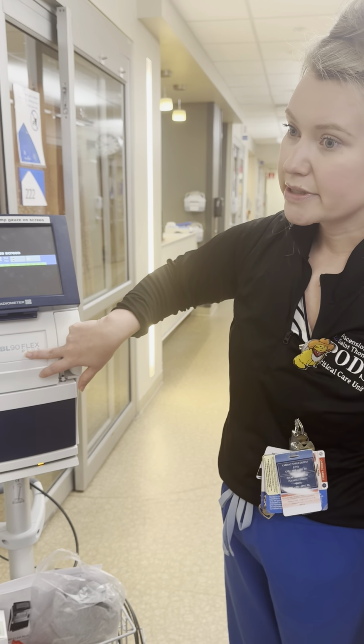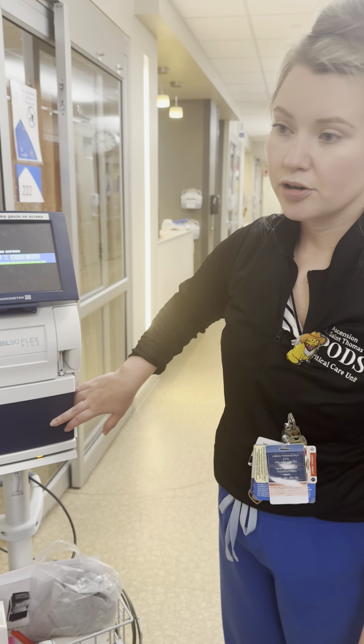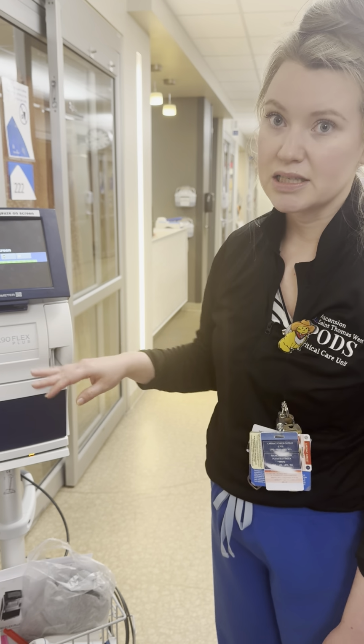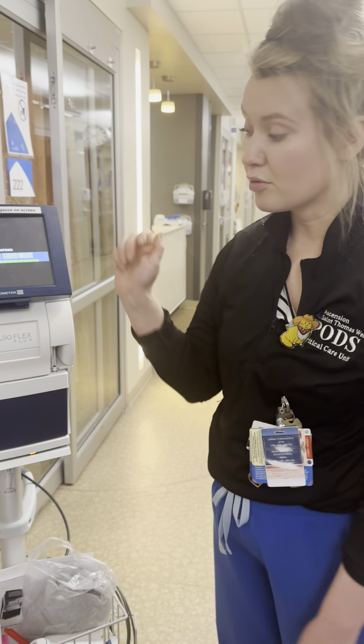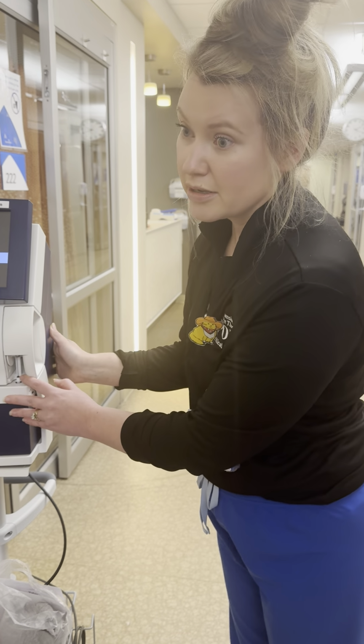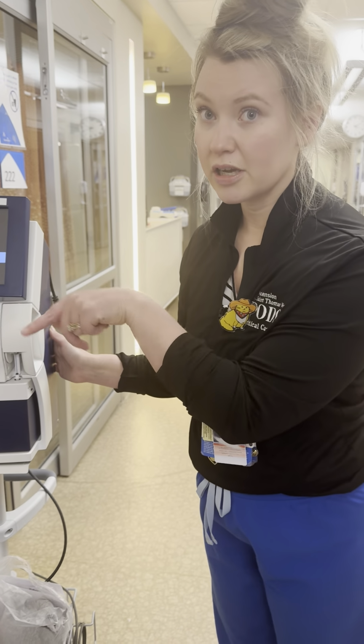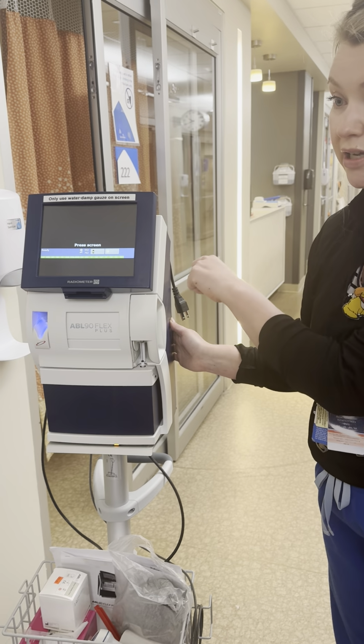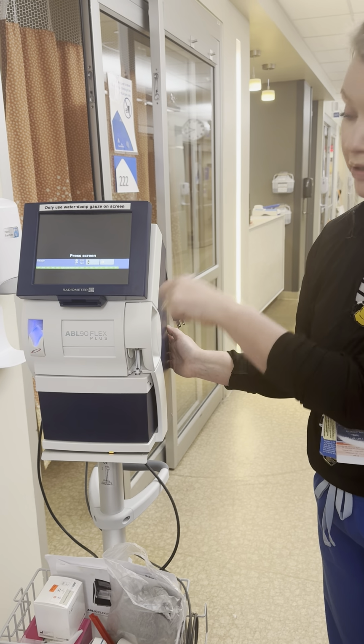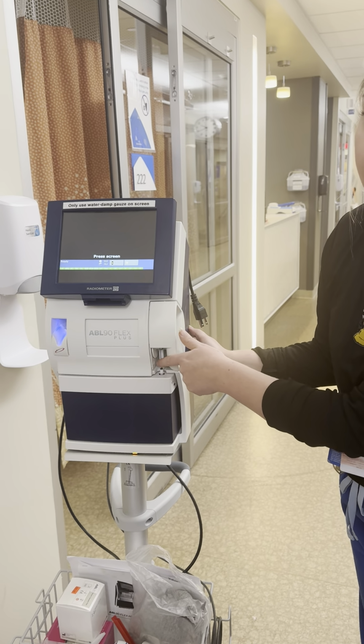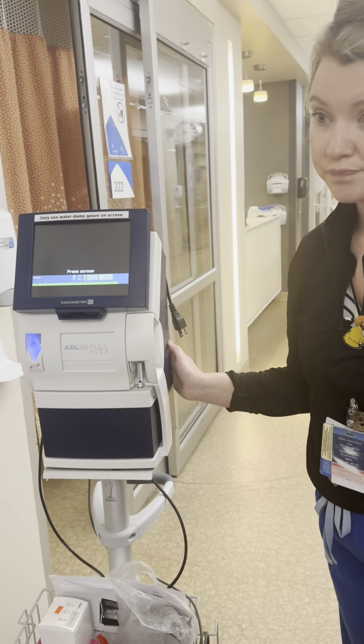Underneath here you've got a sensor cassette, and this is a big sample pack. There are no cartridges like with the iStat. Everything that you need is built in the machine. You're going to take your sample and you're going to touch it directly to this probe. So when you hit that you're ready, it pops out, and you're going to take your syringe, you're going to touch it and push it in, and it's going to draw your sample from there. This little metal probe is not a sharp, but it's going to drop down into your syringe.